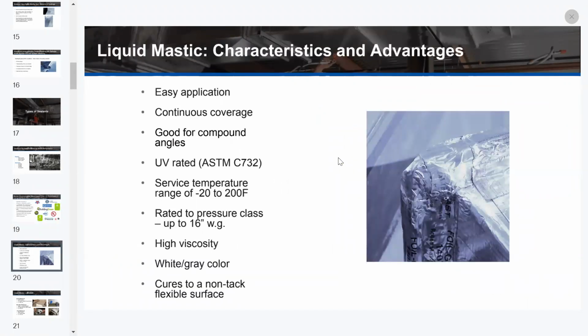So a liquid mastic, some of the characteristics and advantages. If you're looking at a liquid mastic, it's easy application, it's continuous coverage, it's really good for compound angles. Typically you have UV rating on those, so they can be used indoor and outdoor. Have a wide service temperature range of -20 to 200 degrees Fahrenheit. Rated to pressure classes up to 16 inches of water gauge. I know for our company in particular, we do third-party testing of that. They're typically a high viscosity, so they're nice and thick, easy to put on the duct and stay in place. It's offered in two colors, white or gray, or some version of gray. And it cures to a non-tack flexible surface.